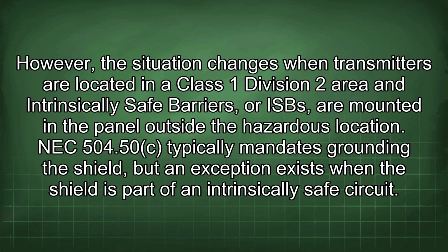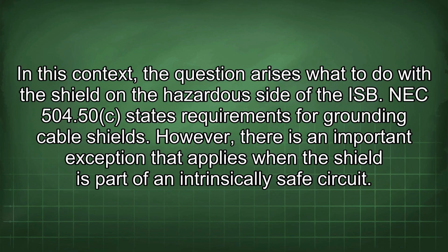However, the situation changes when transmitters are located in a Class 1 Division 2 area and intrinsically safe barriers, or ISBs, are mounted in the panel outside the hazardous location. NEC 504.50 typically mandates grounding the shield, but an exception exists when the shield is part of an intrinsically safe circuit. In this context, the question arises what to do with the shield on the hazardous side of the ISB.